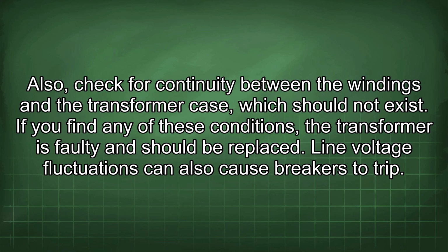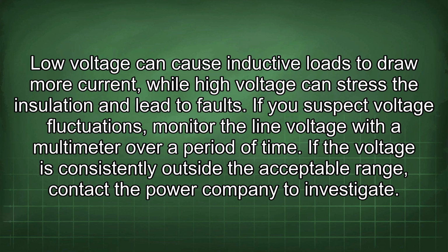Line voltage fluctuations can also cause breakers to trip. Low voltage can cause inductive loads to draw more current, while high voltage can stress the insulation and lead to faults. If you suspect voltage fluctuations, monitor the line voltage with the multimeter over a period of time. If the voltage is consistently outside the acceptable range, contact the power company to investigate.